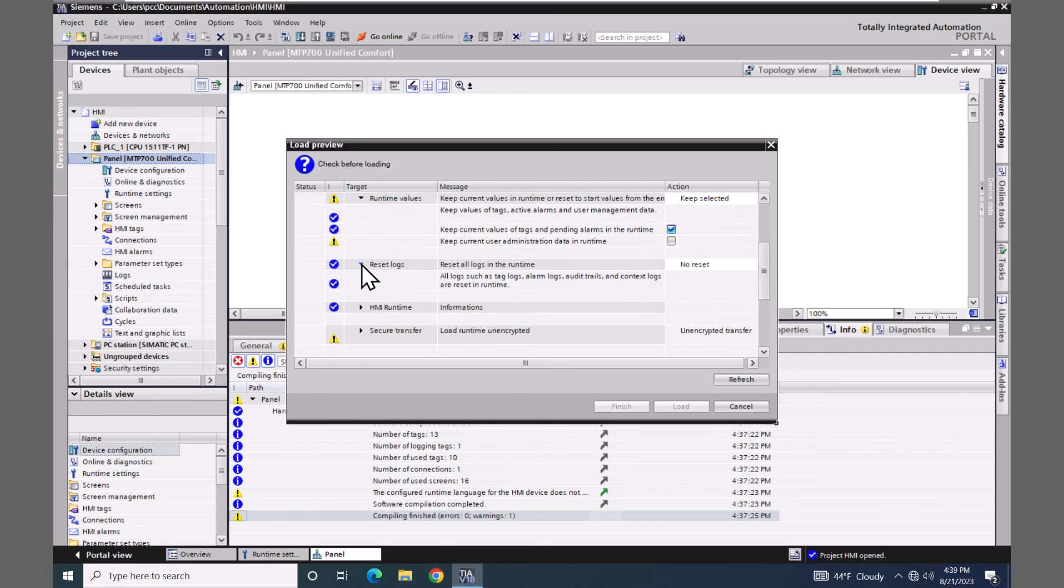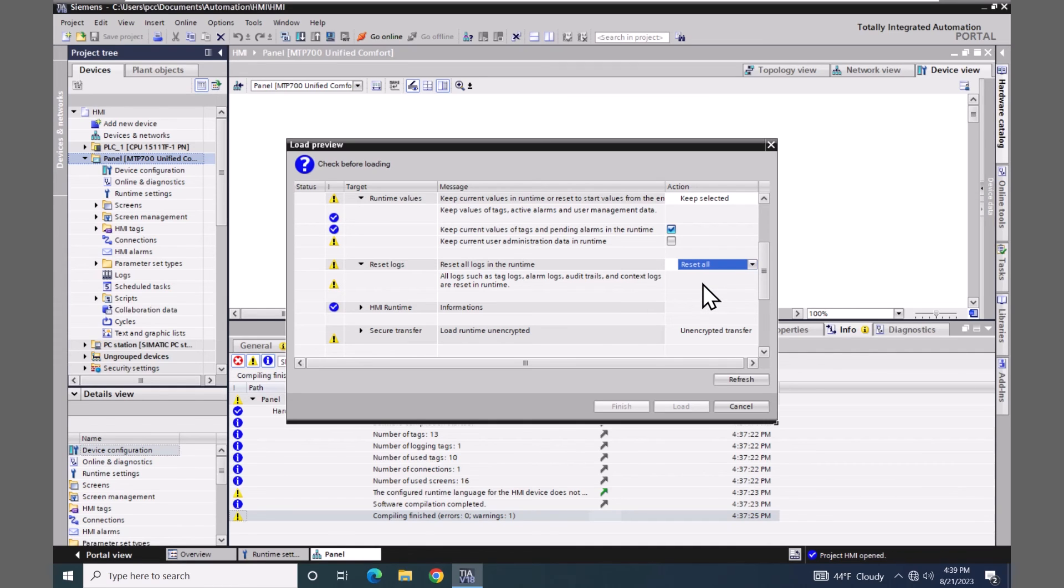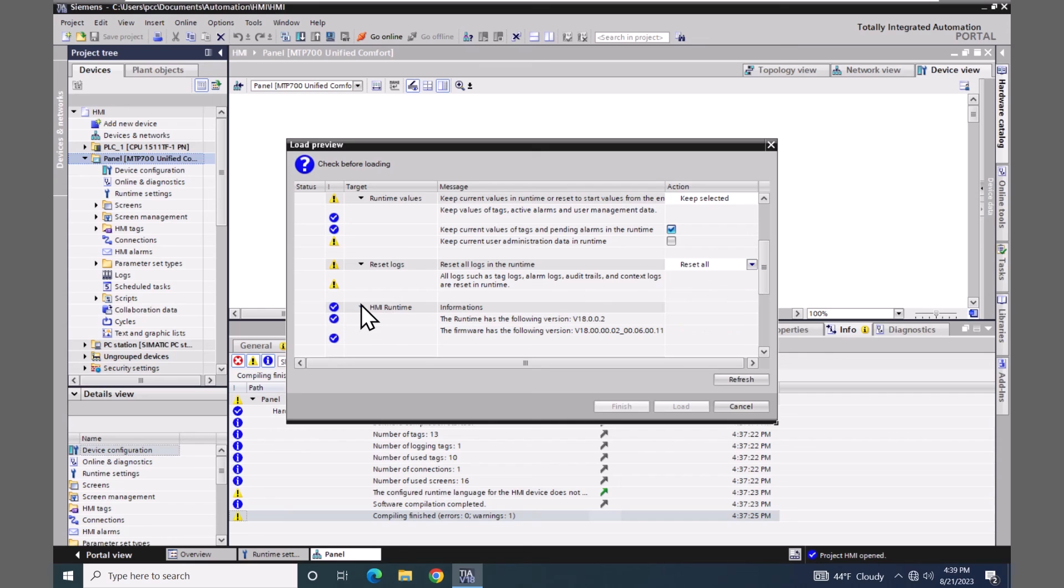There is an option to reset the logs. Right now it's set to no reset, but I could change that to say reset all if I wanted to, and then that would delete or reset them on the unified comfort panel. You also do have an option for the HMI runtime where you can actually see the versions that are already loaded on this particular HMI. So if there is a discrepancy here you would be able to see the differences as well.